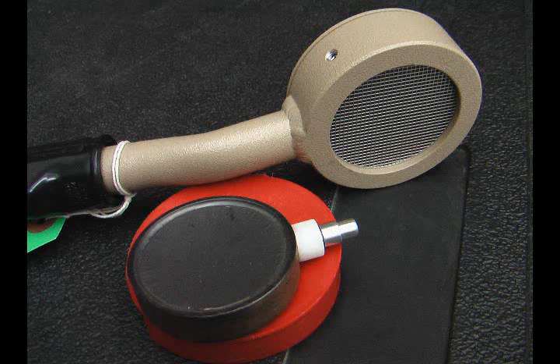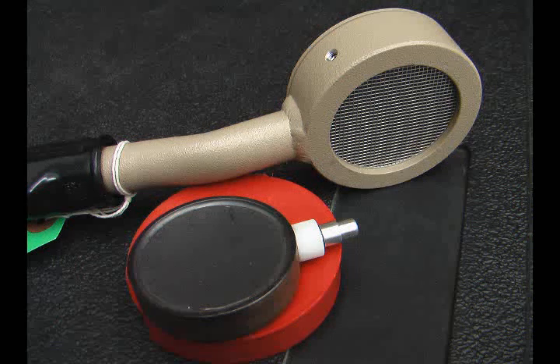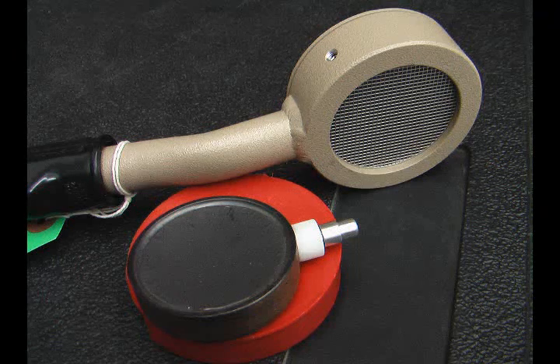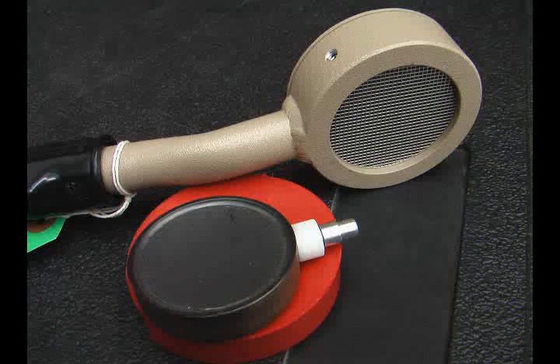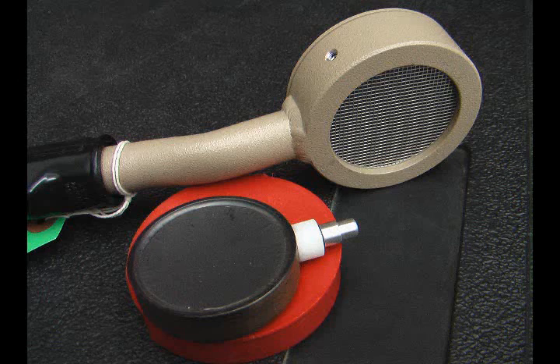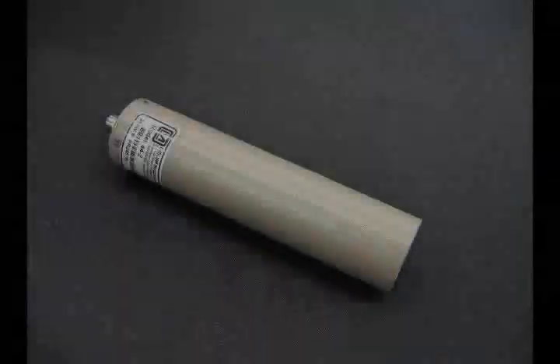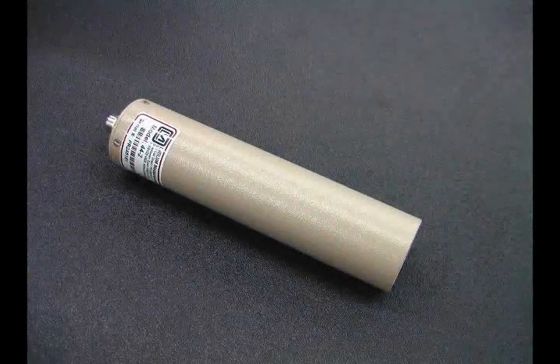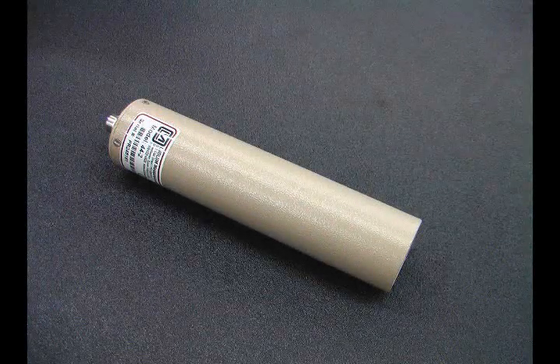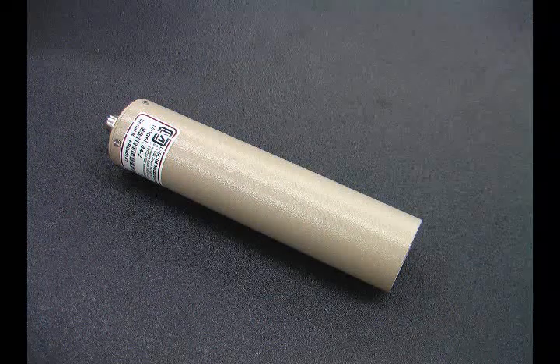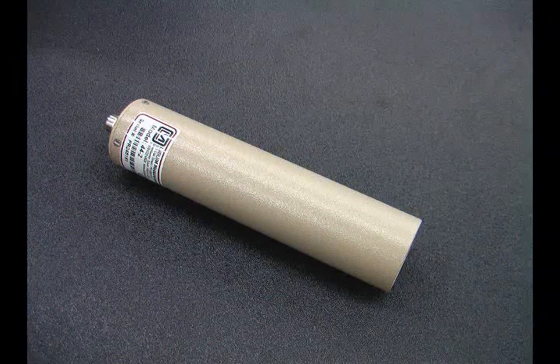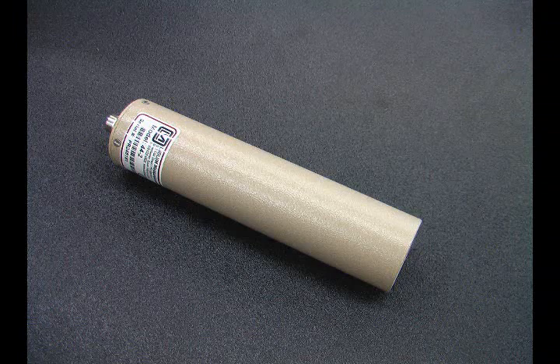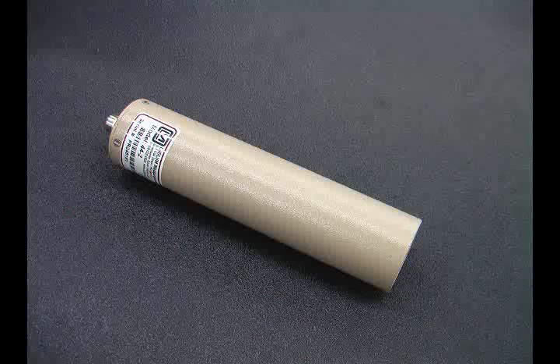Caution should be taken when using the detector around vegetation or any sharp objects. The thin mica window is easily damaged. The plastic cover should be used to protect the window when not being used. The GM tube can easily be removed for replacement if necessary. The Model 14C response kit also contains a Model 44-2 sodium iodide gamma scintillator. It consists of a sodium iodide crystal coupled to a photomultiplier tube and is housed inside thick aluminum.